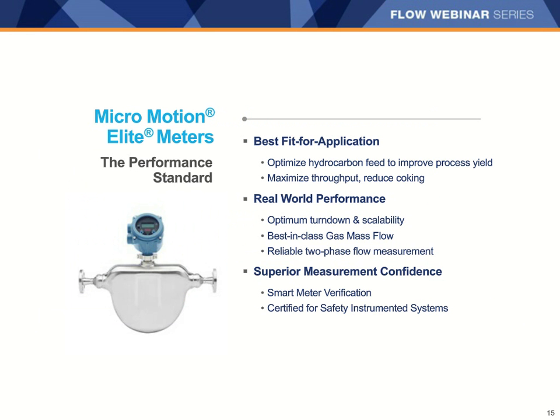Micro Motion meters offer superior performance under real-world conditions. The Elite flow meters provide the best measurement for the hydrocarbon feed to help optimize the ratio and improve the conversion while reducing coking. They offer up to a quarter percent mass flow accuracy for gas, which is unmatched, and that accuracy applies over a really wide range of flows. Micro Motion also offers advanced diagnostics that can give you more confidence that your meter is working correctly without interrupting the process. For safety instrumented systems, Micro Motion offers both certified and proven in-use devices good for up to SIL 3 applications.